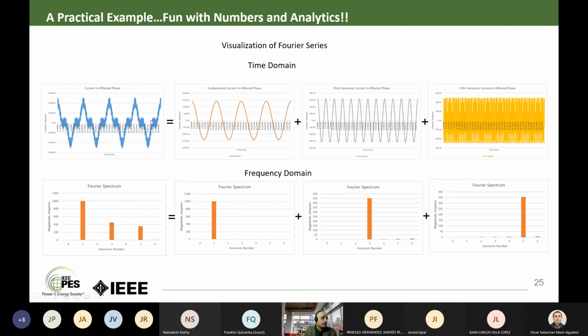In the time domain, this current waveform equals the waveform at the fundamental frequency, plus the third harmonic, plus the fifth harmonic in this case. In the frequency domain, this shows 1000 amps at fundamental, a little more than 400 amps at the third harmonic, and some fifth harmonic. This is the Fourier spectrum for each case - you guys are familiar with this, right?